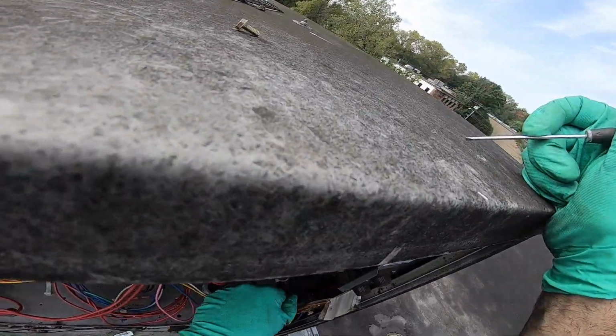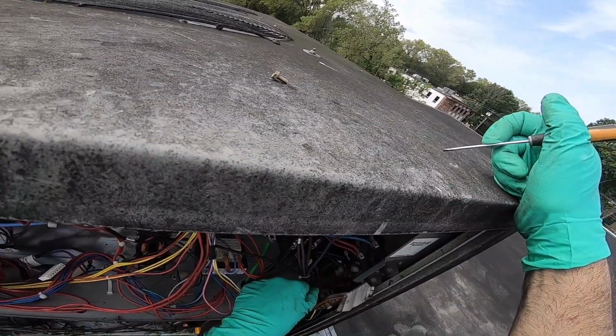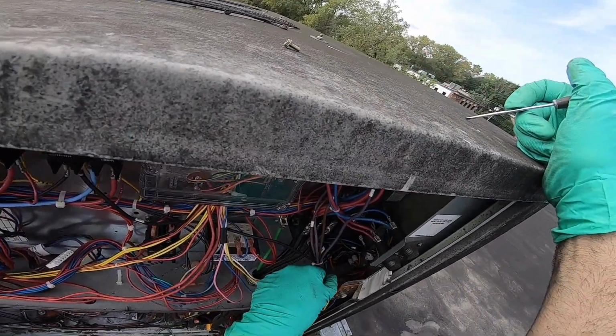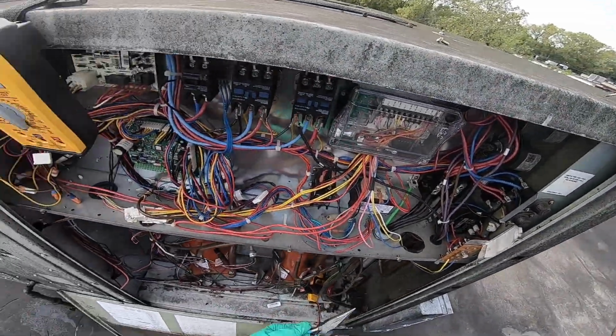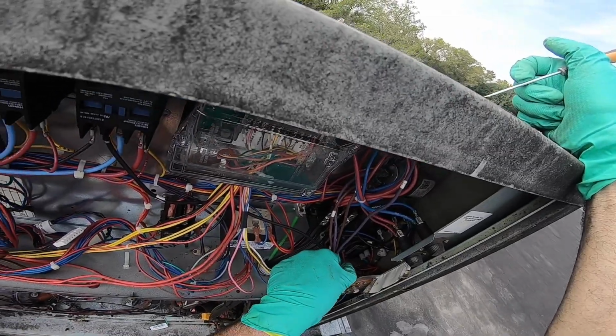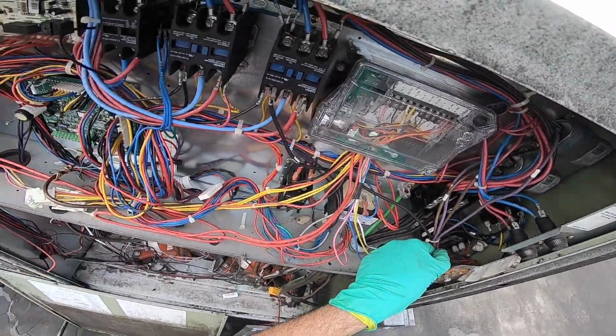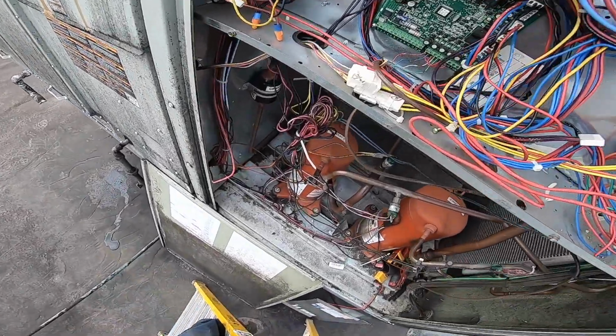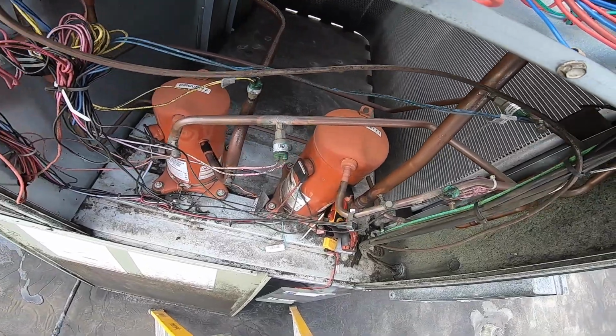Okay, fan. Compressor. Compressor two. About time the test started working for me. Heat, whatever, we'll go heat. Oh no, compressor two. Boom, off. Heat. I could have sworn I heard the compressor two come on earlier, but there goes the heat.